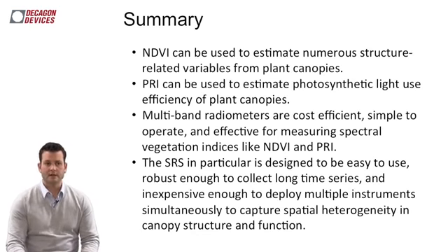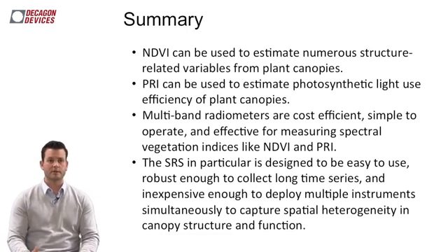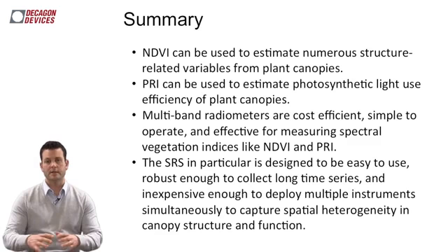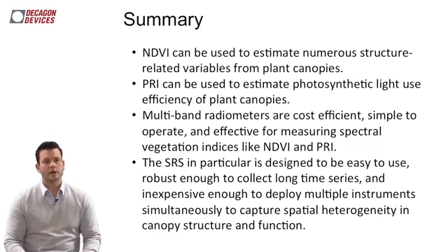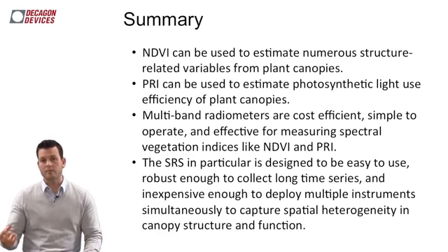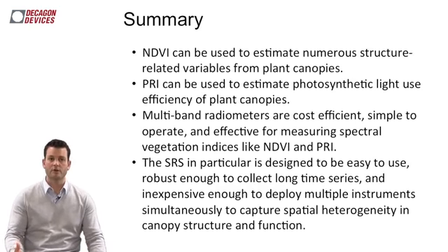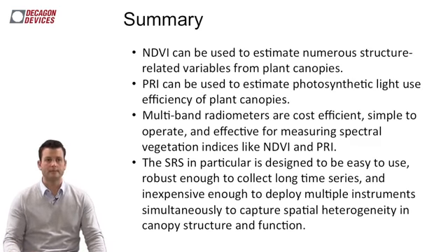A couple reasons I say that is that the SRS is relatively low cost. It's robust, so like I said, it's epoxy filled, which really means that it's designed and capable of being left out in all environmental conditions without having to worry if the sensor is being destroyed or not.